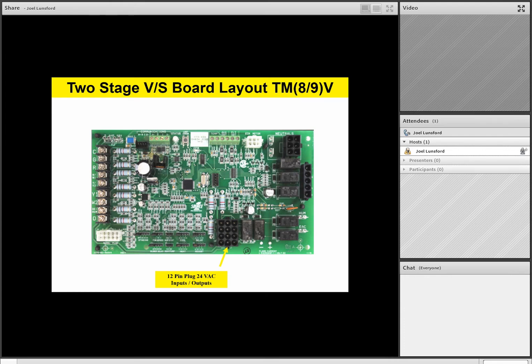So the first one we're going to talk about is our delay jumper. That delay jumper is to adjust our ramping operation for cooling on delay. So please write that down or make a note. The cooling on delay function will be utilized with that delay jumper A, B, C, or D. And it should be noted that we normally ship it in the A configuration, which is normal. And what that tells us is the fan takes about 30 seconds to ramp up, and then it's at full airflow after about 30 seconds.